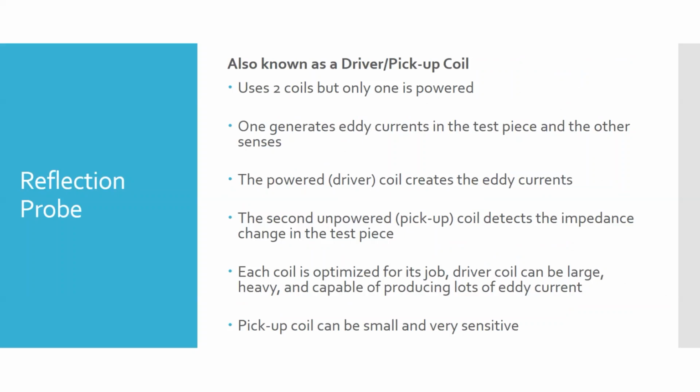When you're using any of these probes, if you overwhelm it, you'll get an indication on your display. I'll show it in lab when we do the demo. I'm trying to remember the exact wording on it, but it's essentially an oversaturation box that comes up. It tells you you're getting a lot of distortion and feedback in your coil. And if you're getting that, your results are not acceptable. That's basically a false indication. So these reflection coils help to minimize that from occurring.